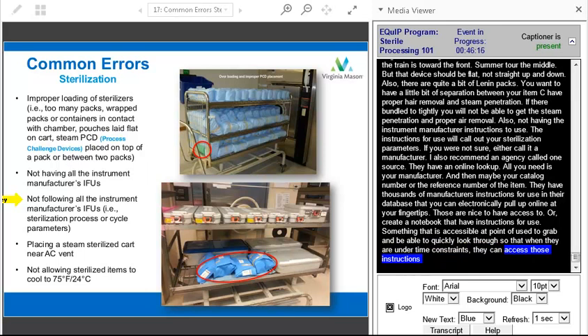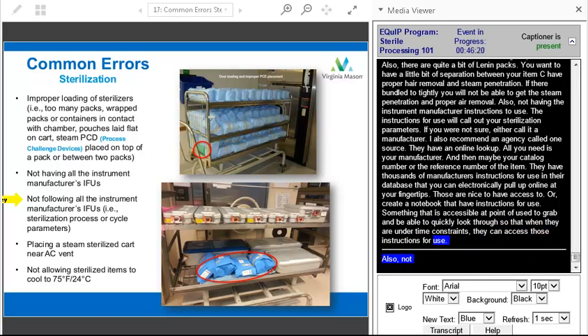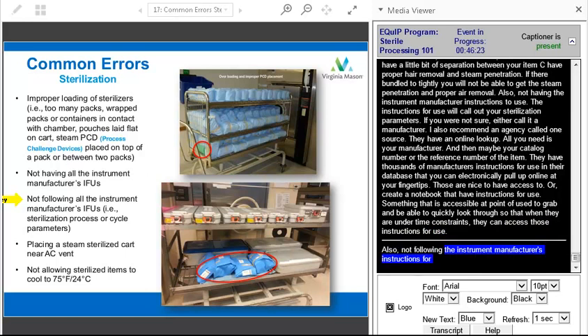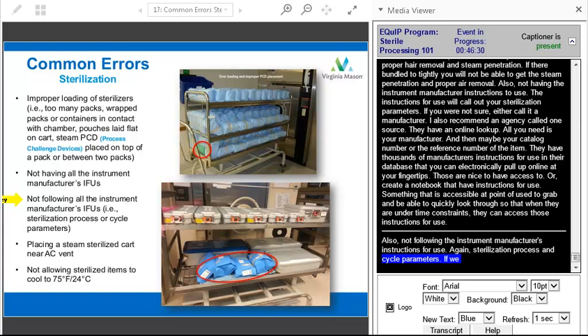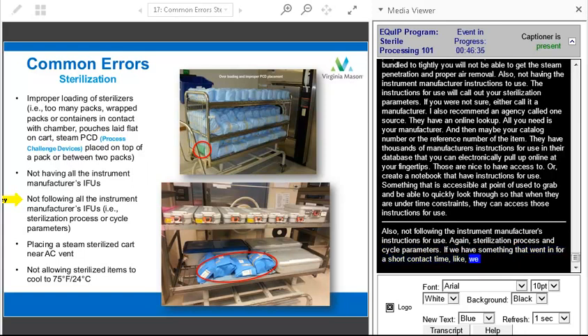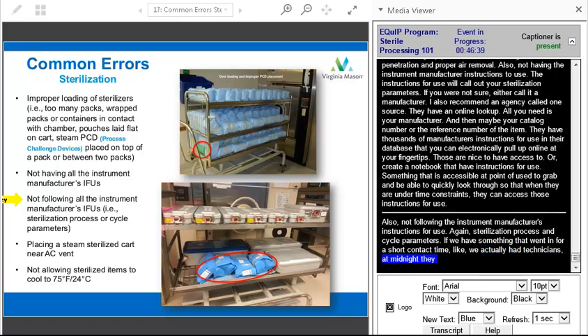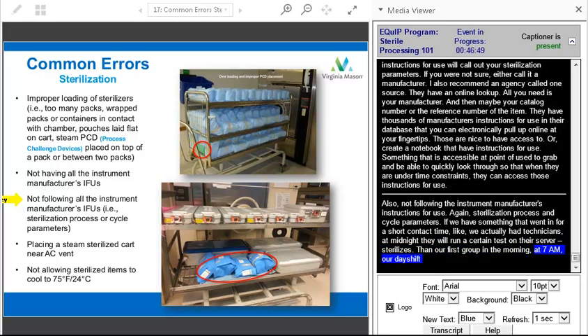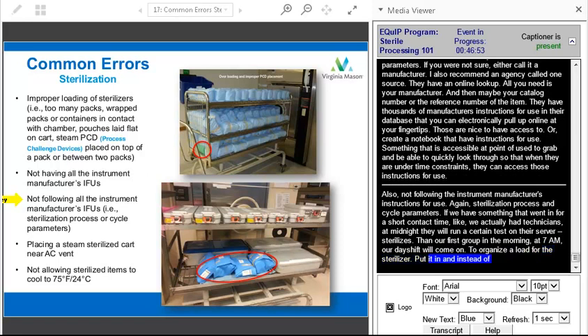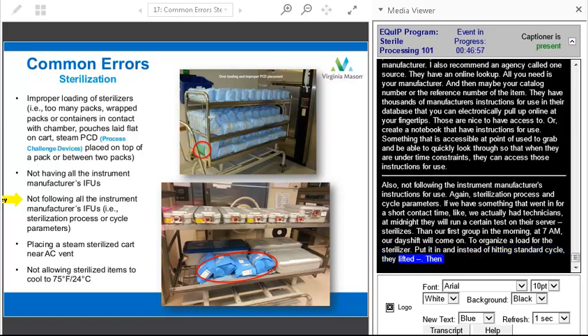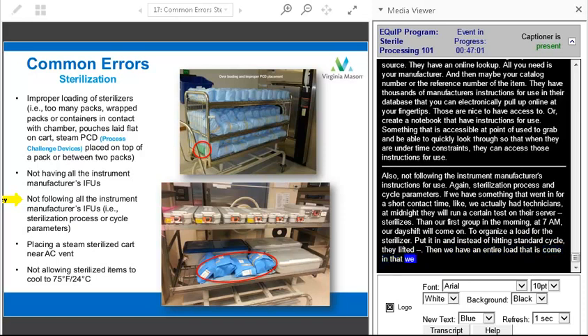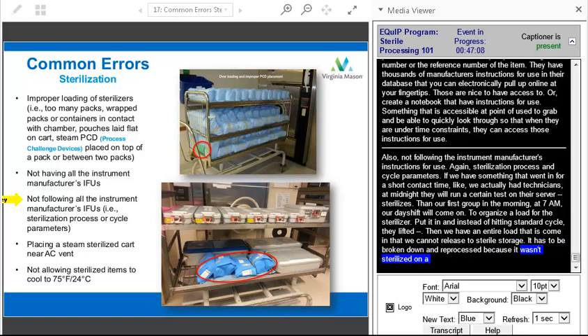And then also not following the instrument manufacturer's instructions for use. Again, for example, sterilization process and cycle parameters. So if we have something that went in for too short of a contact time, we've actually had technicians who, at midnight, will run the Bowie-Dick test on their steam sterilizers. Get those all good, and then our first group in the morning at 7 a.m., our day shift, will come on. They'll organize a load for the sterilizer, put it in, and instead of hitting standard cycle, they've left it on the Bowie-Dick test. And so then we have an entire load that's come in that we cannot release to sterile storage. It has to be broken down and reprocessed because it wasn't sterilized on the proper cycle or sterilization parameter. So attention to detail like that is also important.